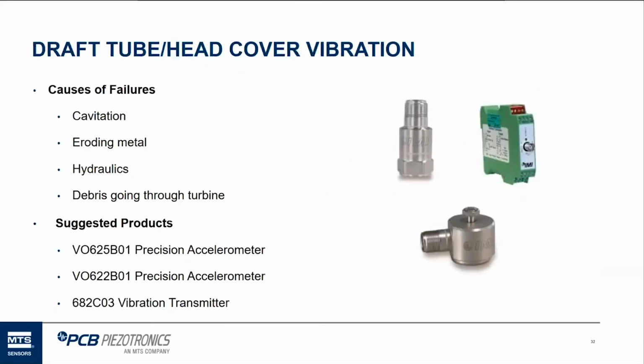Draft tube and head cover vibration, kind of caused by a lot of the same issues we talked about, are also if some debris is able to make it past the screen and go into the turbine. We've got various sensors and transmitters for detecting this and able to provide output based on this. Our velocity output series accelerometers, and we've got a vibration transmitter as well, which these sensors can run into and provide a 4 to 20 milliamp output for feedback into a PLC system.